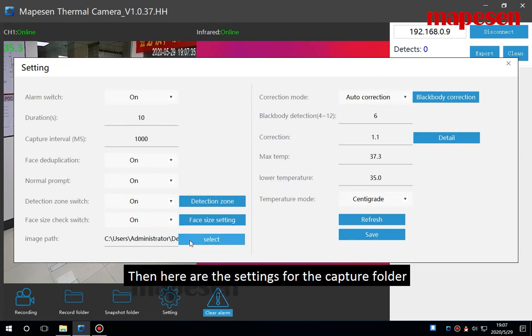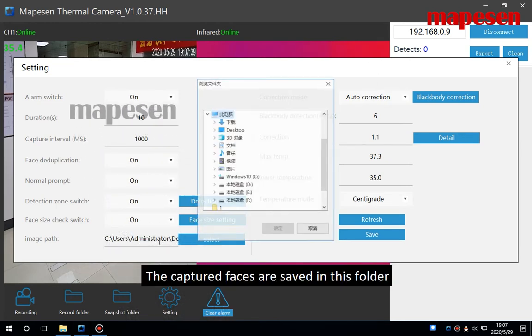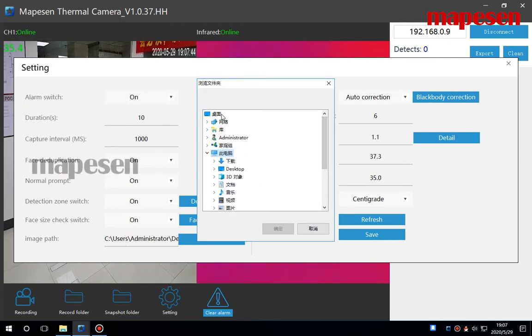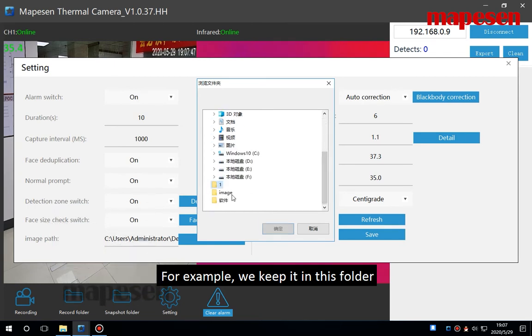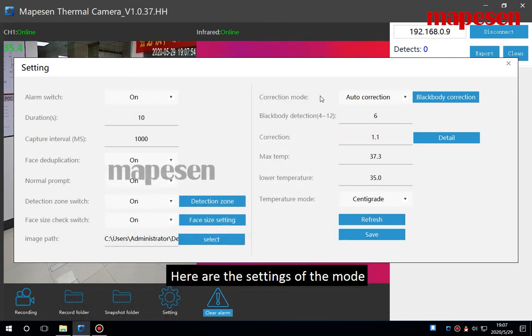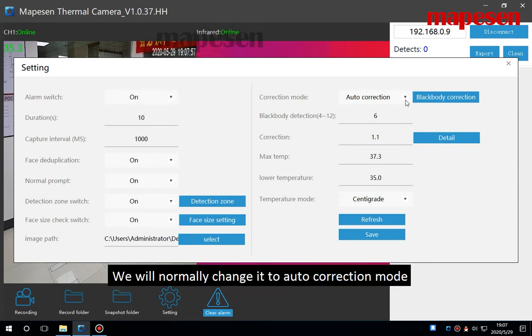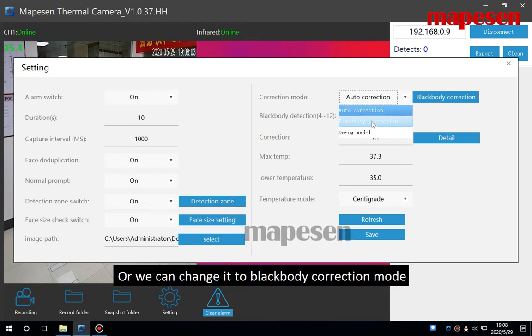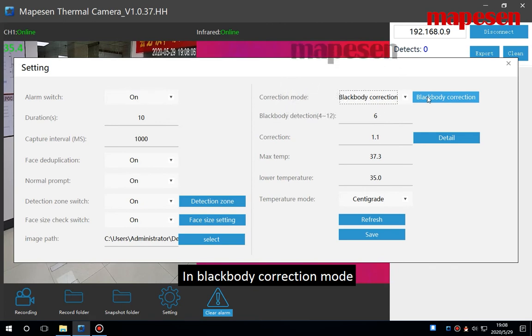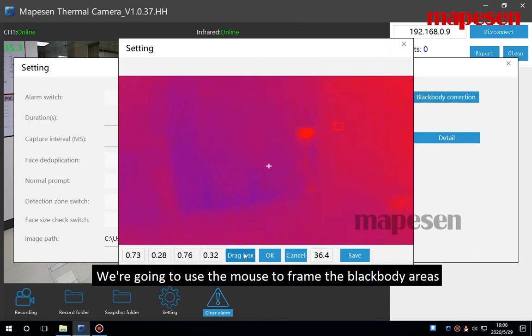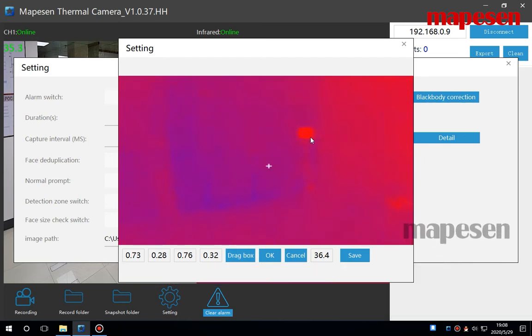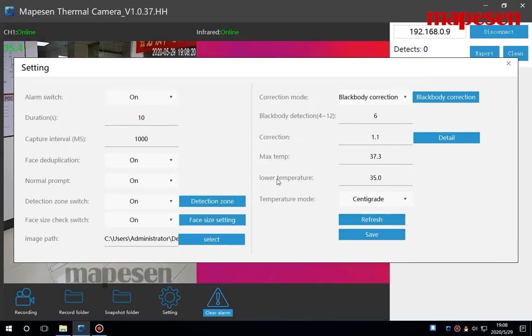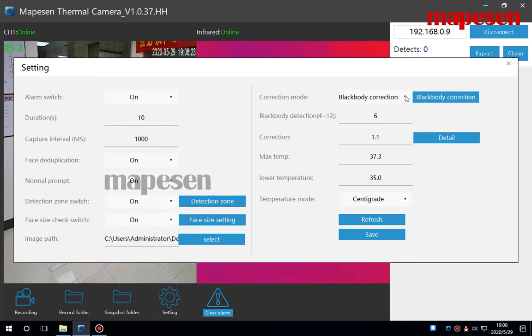Then here are the settings for the capture folder. The captured faces are saved in this folder. For example, we keep it in this folder. Here are the settings of the mode. We will normally change it to auto correction mode, or we can change it to blackbody correction mode. In blackbody correction mode, we need to click this to match the blackbody. We are going to use the mouse to frame the blackbody area, then click OK, click save. This is the blackbody correction mode.